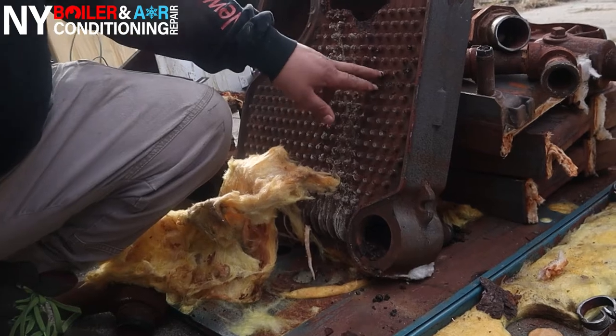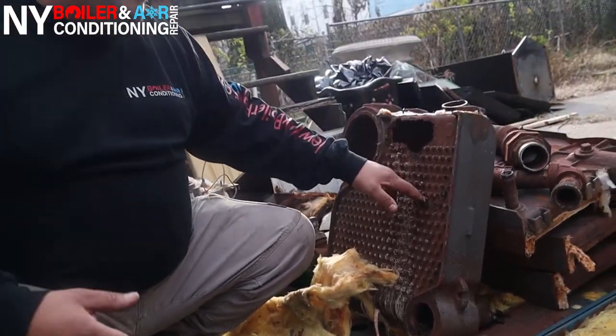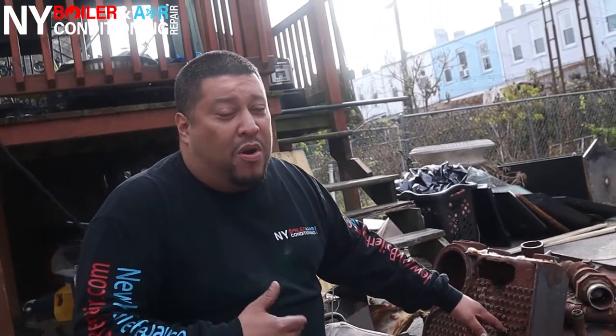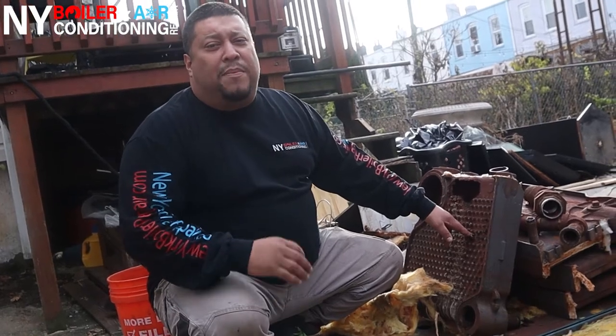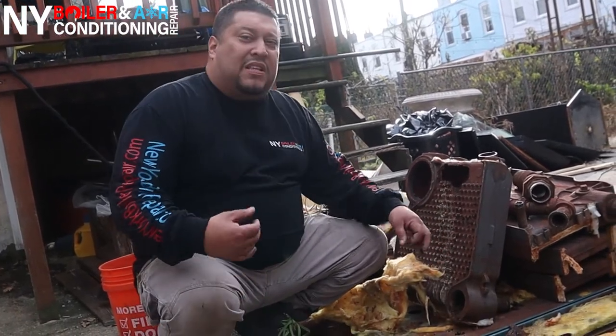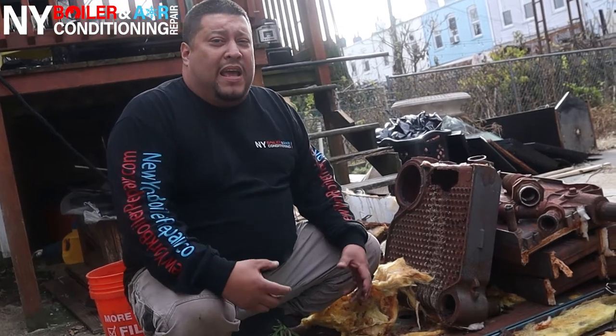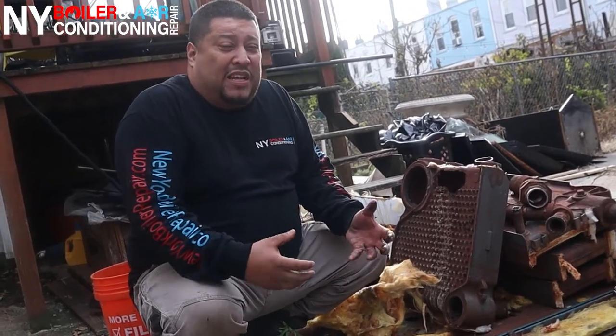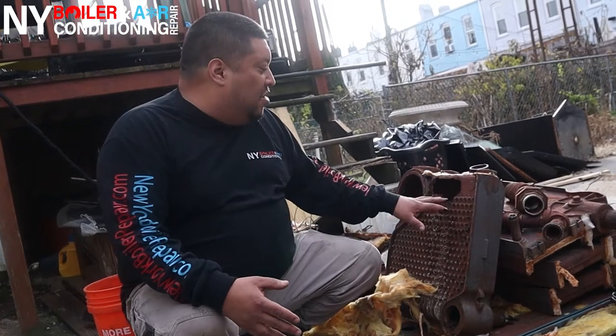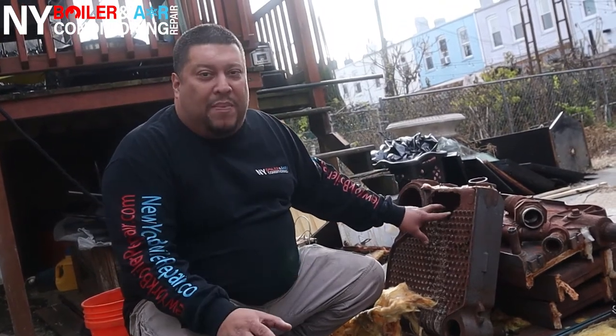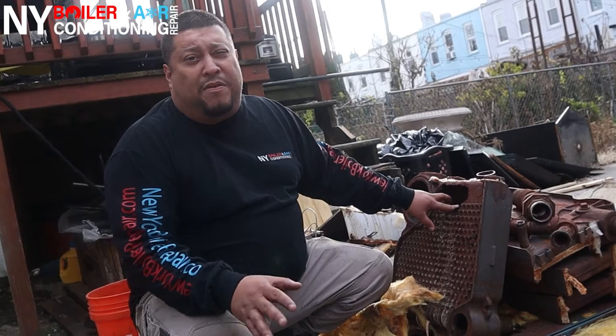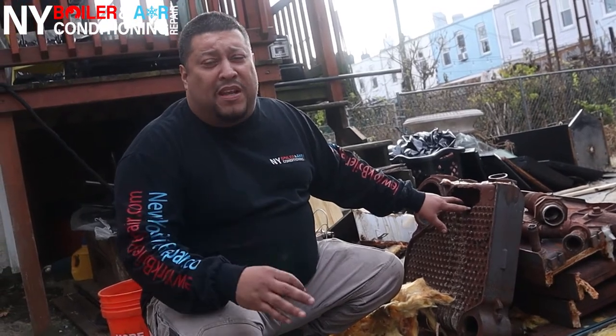But most importantly, they didn't do their preventive maintenance, they didn't do their due diligence. So this is what I tell you guys: it's super, super important. Unless you want to be paying me or any other boiler guy or plumber a few grand a year - listen, I'm okay with it - but the point is, you don't want to do that. Do your due diligence, do your preventive maintenance, because this mud stays inside here and what happens is you don't get enough heat transfer. You're overheating the block, it gets super hot, and one day it's just going to crack. That's exactly what happened, but in this case it's a little different because it corroded. My point is, you don't want to get to this very big expense, so do your preventive maintenance, do your due diligence.